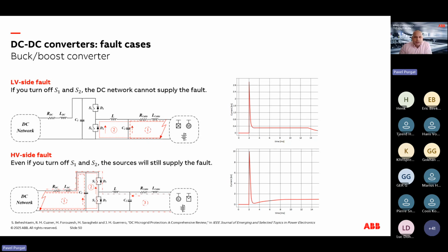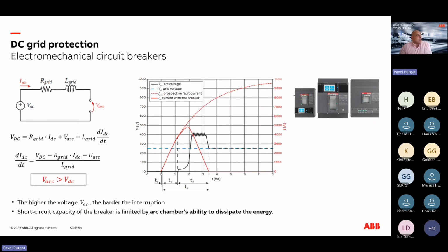So what are the devices that are available? The most standard device is, of course, a DC circuit breaker, which provides direct suppression of the fault. Now, the key for the operation of a DC circuit breaker is that the voltage in the DC system is lower than the arc voltage. Otherwise, the arc will not be extinguished and the circuit will continue to arc. Now, this method is very reliable and very robust. However, it takes several milliseconds or tens of milliseconds in a large system to operate.